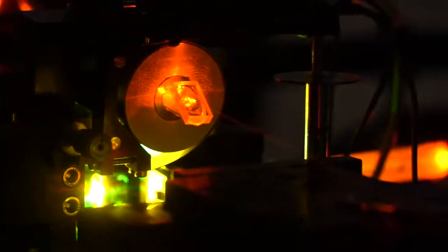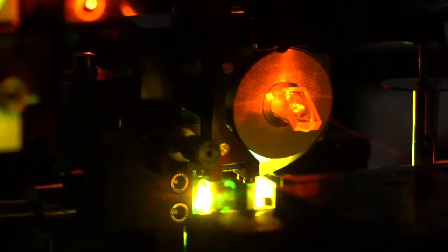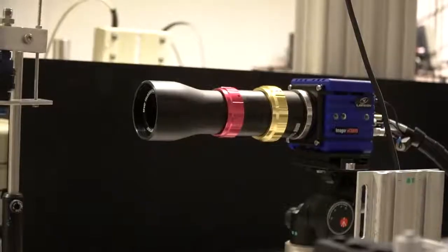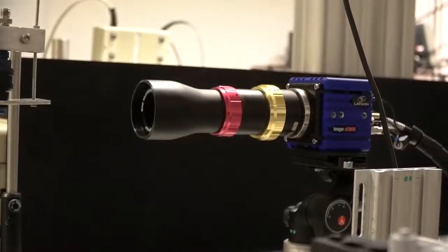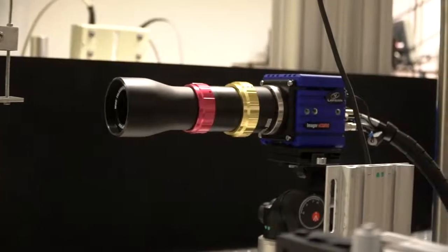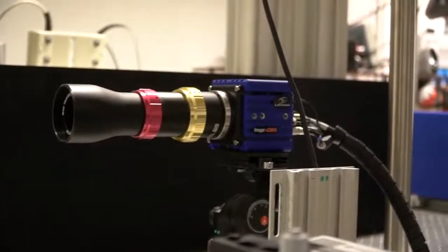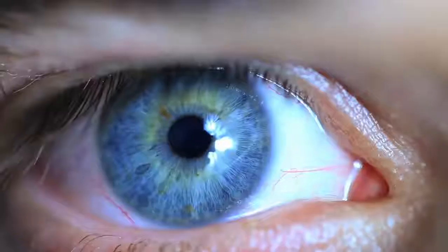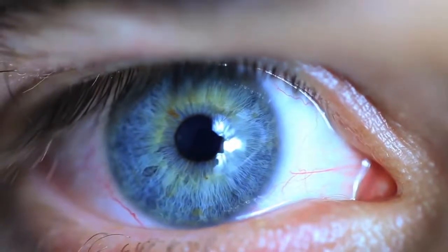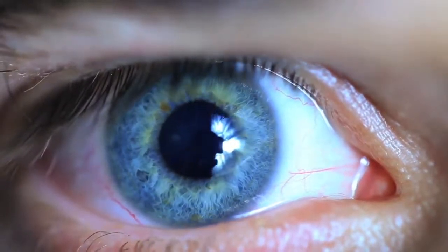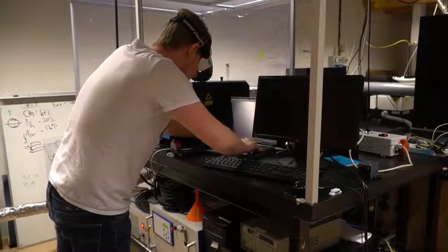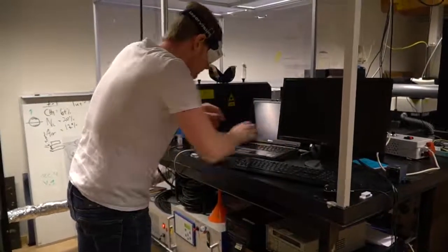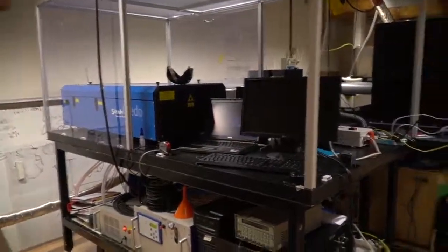When aligning a system, use an alignment laser if possible, or alternatively, reduce the power of your laser for this procedure. A good option may also be to use cameras when aligning the system, if possible, rather than doing it by eye. Remember that in low light conditions, the pupil in the eye will expand, which may change safety calculations. Always work with good lighting in the lab if possible.